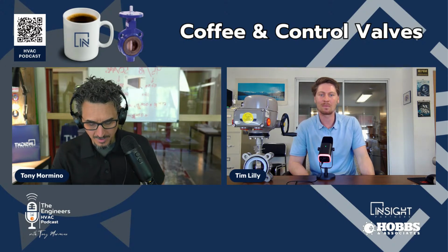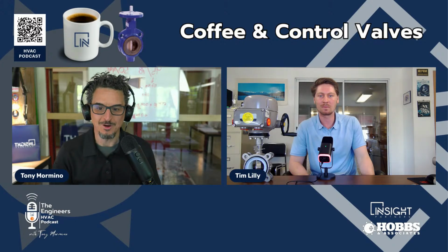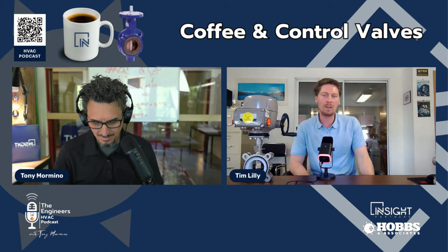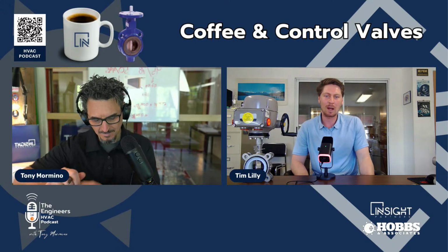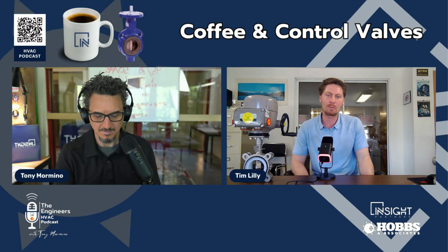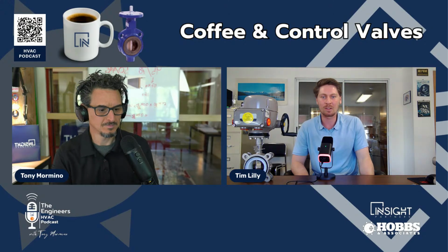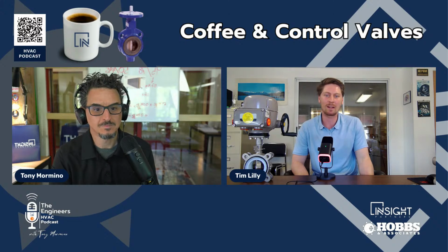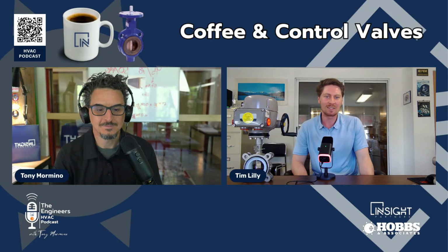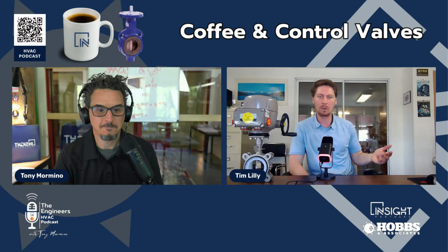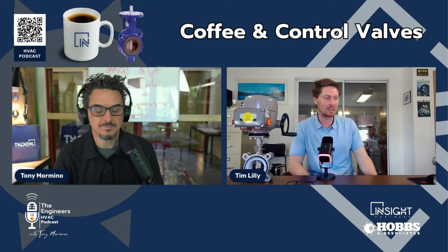What are the best practices for maintaining chilled water and hot water valves? Is there a lot of maintenance involved? There's not, and most butterfly valves are what they call throwaway valves. I quoted an 8-inch butterfly valve yesterday for $800, so it's not worth your time to maintain it and buy a repair kit to fix it. After all the labor that goes into it, you're better off just putting in a new valve. If you have an expensive control valve it changes a little bit, but otherwise it's a very simple device, which is nice.